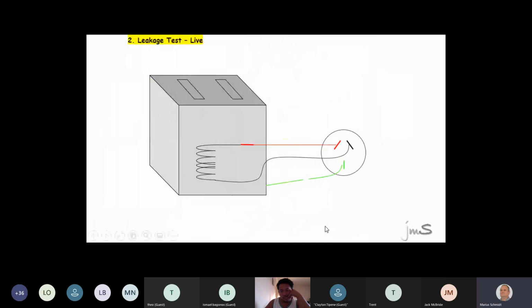If I ask you to do a leakage test, we call this a live test. Now, I bet you've done this before. First test you do, you first check the earth. What is the maximum ohm reading of the earth? Is it 1 ohm or half ohm? Appliance, 1 ohm. Can't be more than 1. Can it be 0.3, 0.4, 0.7? Yes. What about 1.1? No.